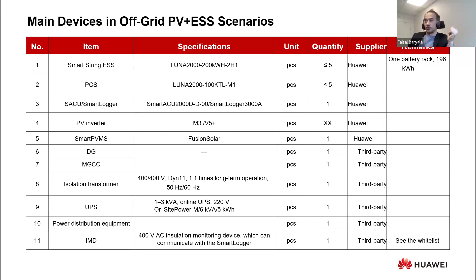So this is exactly the idea behind having an IMD, especially for an off-grid system or when the grid collapses. In order to not make the PCS restart manually, we can connect the IMD to make the insulation resistance test. And every time there is some low insulation resistance, this IMD unit will send information to the smart logger or to SACU, and it will generate an alarm if there is any problem.